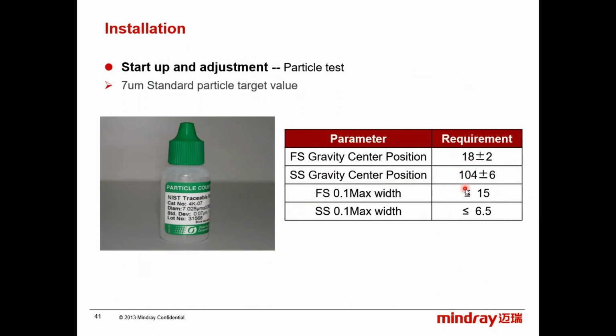For the FS and the SS, if both are very low, it means that you need maybe a very big gain to reach these values, or maybe the CV is out of range. Let's say to get this target 104, you need maybe a gain of 253. This is out of range. So this is probably that the SS photodiode is tired, or has aged.